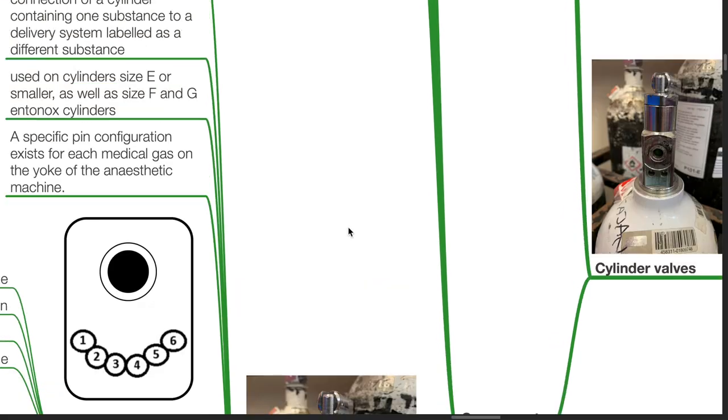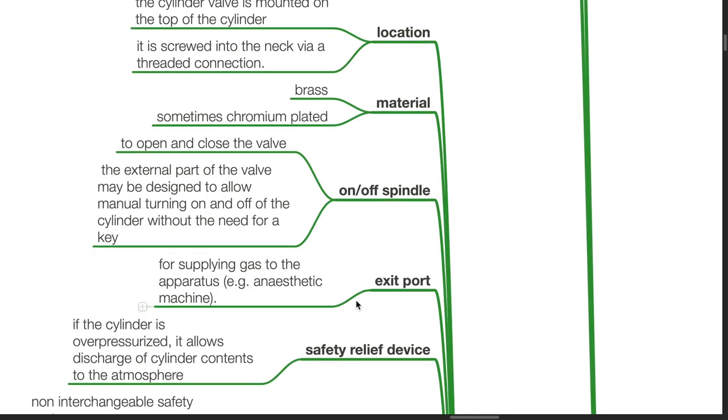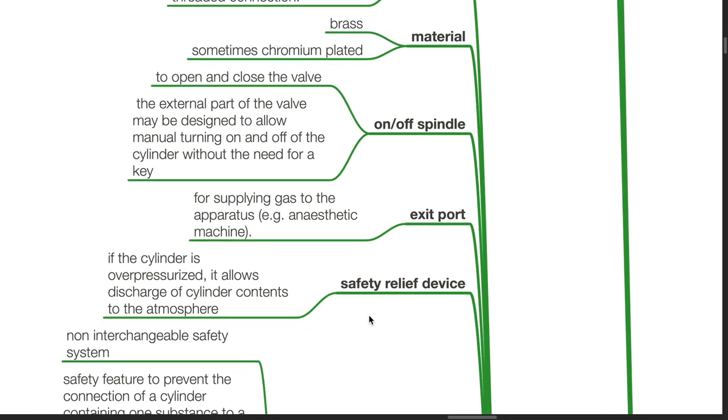Components of the cylinder valve: It is located at the top of cylinder, screwed into the neck of the cylinder via a threaded connection. It is made of brass and is sometimes plated with chromium. There is an on-off spindle to open and close the valve. The external part of the valve may be designed to allow manual turning on and off of the cylinder without the need of a key. Exit port for supplying gas to the apparatus such as an anesthetic machine. Safety relief device: If the cylinder is over pressurized, it allows discharge of the cylinder contents to the atmosphere.